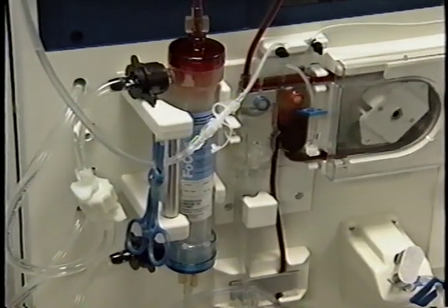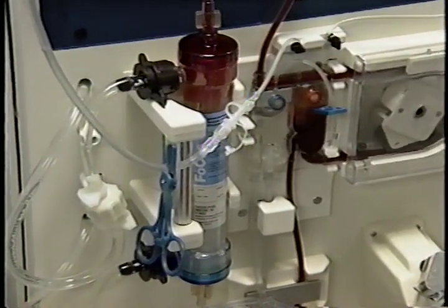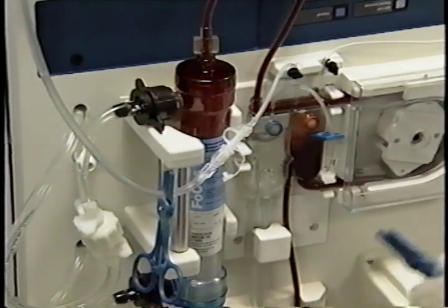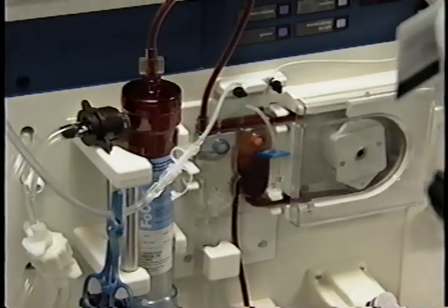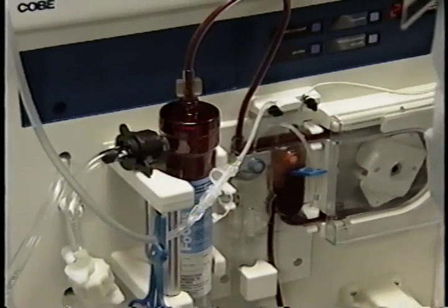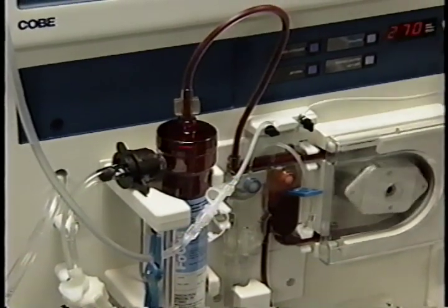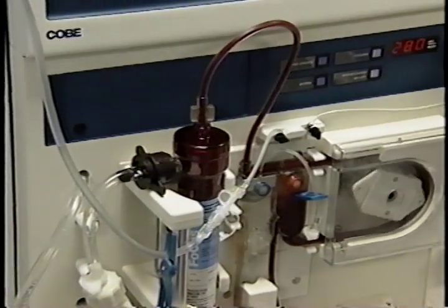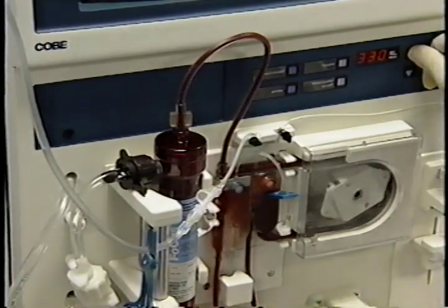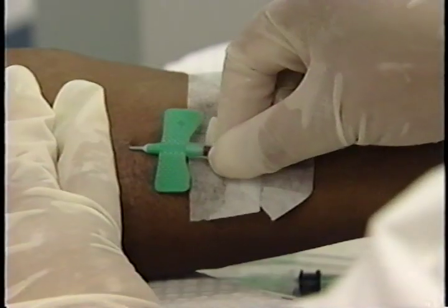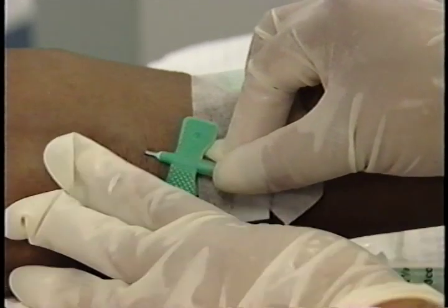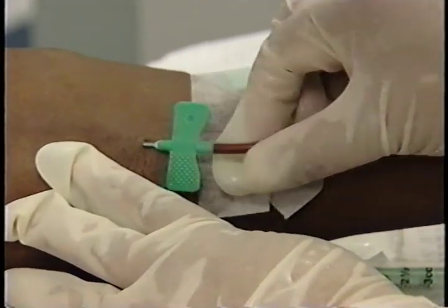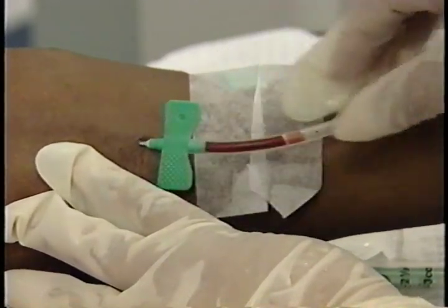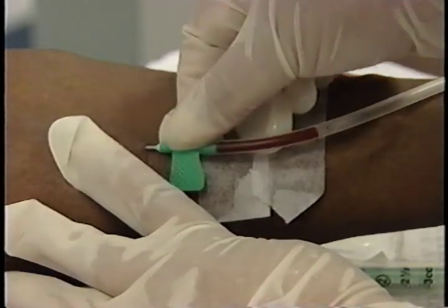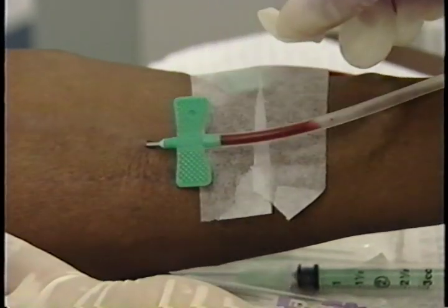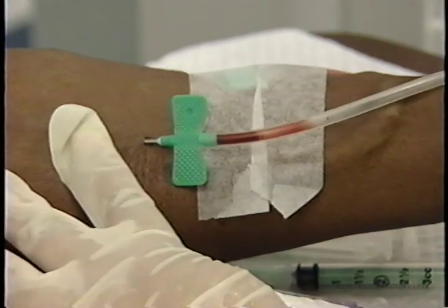The prescription is based on the assumption that the blood flow is constant throughout dialysis. Try to achieve a constant, steady flow of blood through the dialyzer as quickly as possible. If the prescribed blood flow cannot be maintained throughout the treatment, the dialysis time may need to be extended. When blood flow from the vascular access is inadequate, there may be several causes. The most likely reason may be as simple as poor needle positioning, which may allow the bevel of the needle to rest against the blood vessel wall, restricting blood flow.